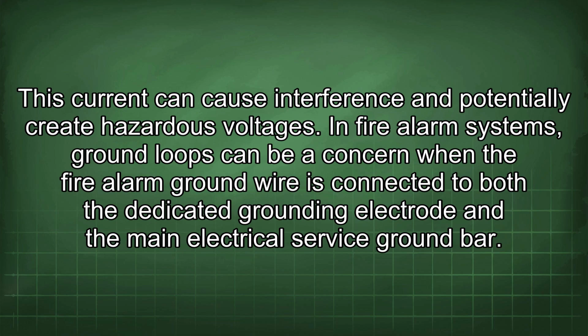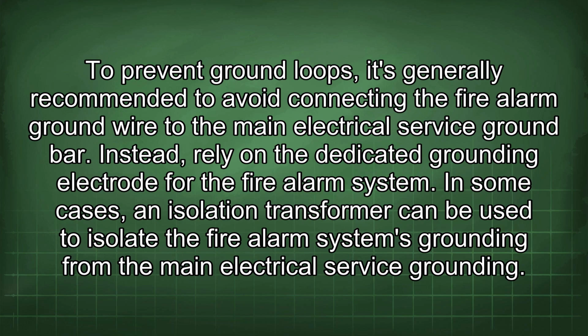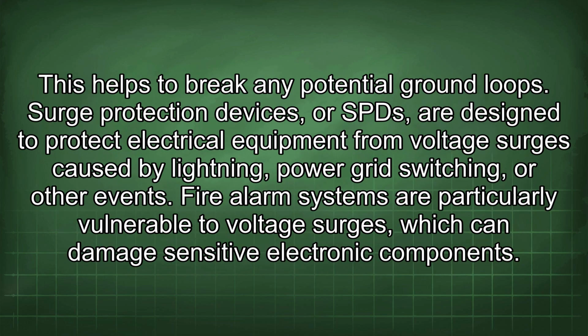In fire alarm systems, ground loops can be a concern when the fire alarm ground wire is connected to both the dedicated grounding electrode and the main electrical service ground bar. To prevent ground loops, it's generally recommended to avoid connecting the fire alarm ground wire to the main electrical service ground bar. Instead, rely on the dedicated grounding electrode for the fire alarm system. In some cases, an isolation transformer can be used to isolate the fire alarm system's grounding from the main electrical service grounding. This helps to break any potential ground loops.